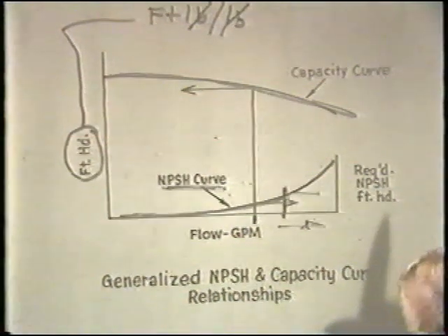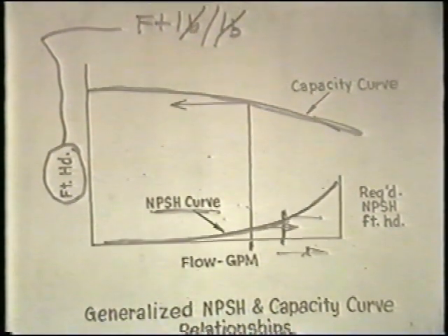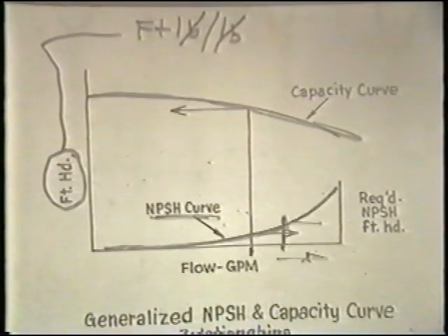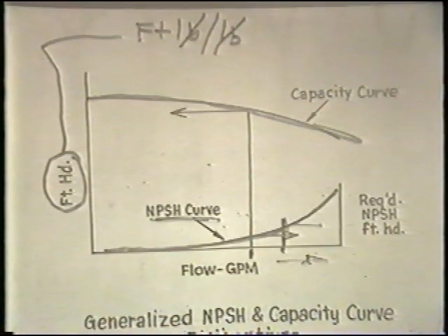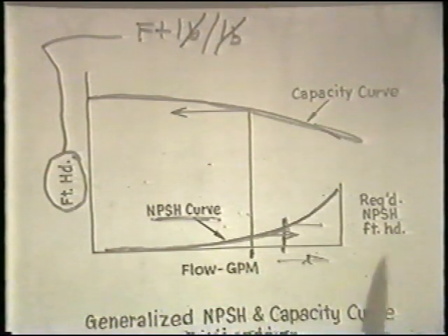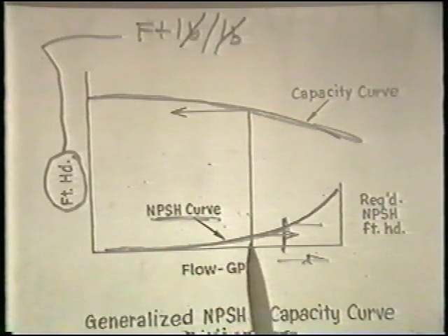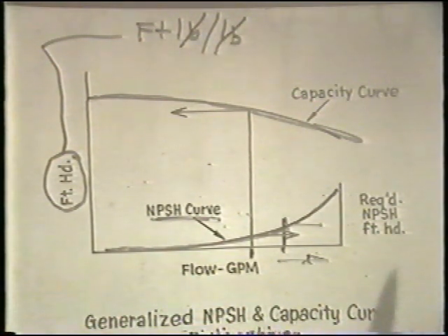So many times we will need a safety factor. But given that we have precise determination of all the considerations given for the pumping of the system, we could use any pump that has a required NPSH less than the available NPSH as shown previously.